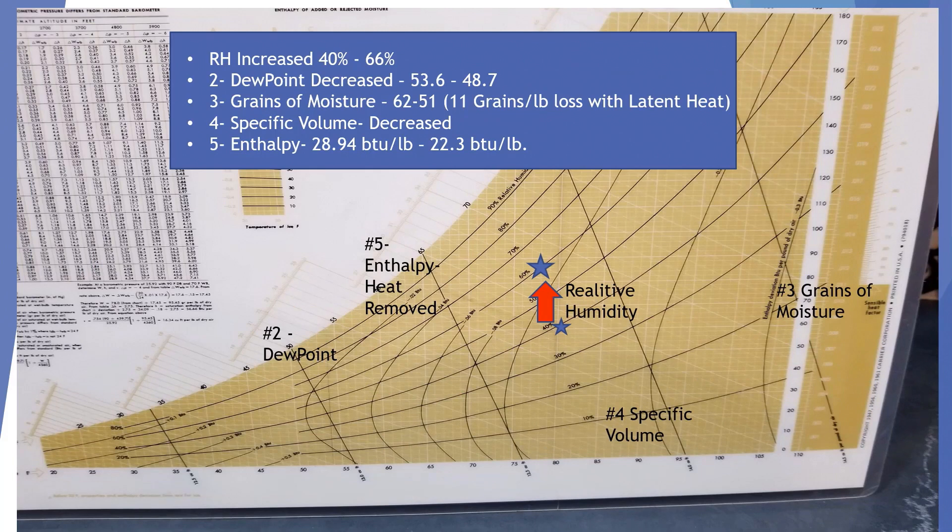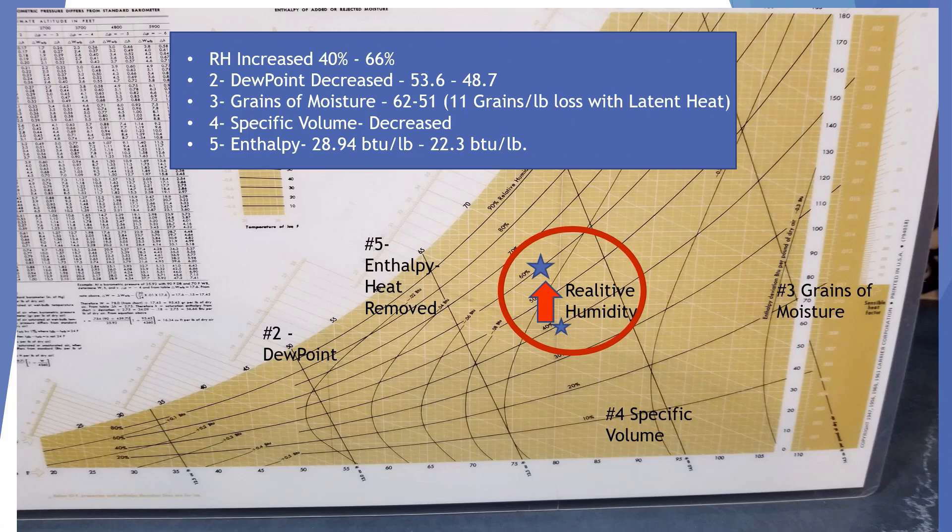So by comparing our numbers that we had on the previous chart, we can see that our relative humidity has increased from 40% to 66%. Our dew point decreased from 53.6 to 48.7. Our grains of moisture went from 62 to 51 grains. So that was 11 grains per pound that we lost with the latent heat process.